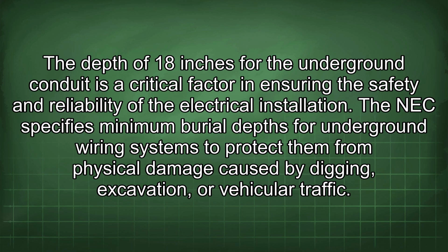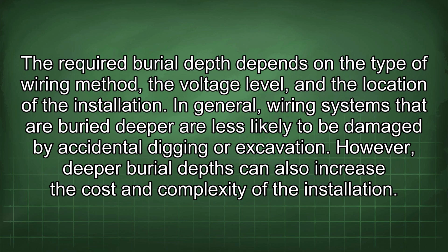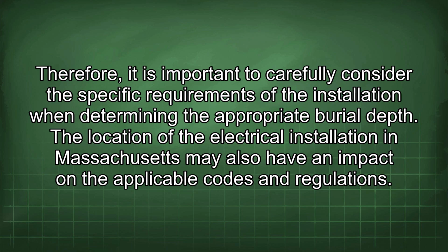The NEC specifies minimum burial depths for underground wiring systems to protect them from physical damage caused by digging, excavation, or vehicular traffic. The required burial depth depends on the type of wiring method, the voltage level, and the location of the installation. In general, wiring systems that are buried deeper are less likely to be damaged by accidental digging or excavation. However, deeper burial depths can also increase the cost and complexity of the installation. Therefore, it is important to carefully consider the specific requirements of the installation when determining the appropriate burial depth.